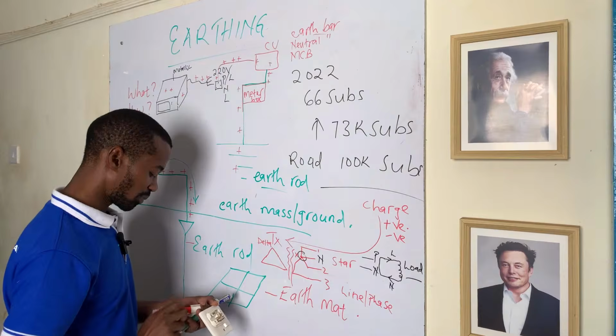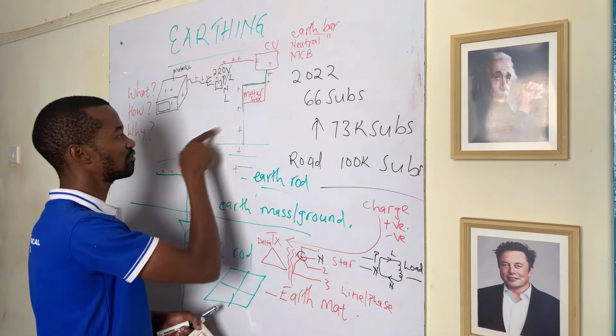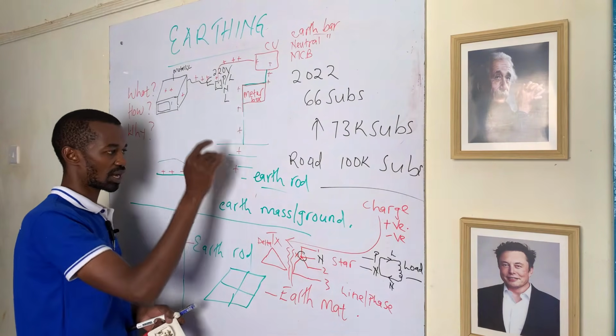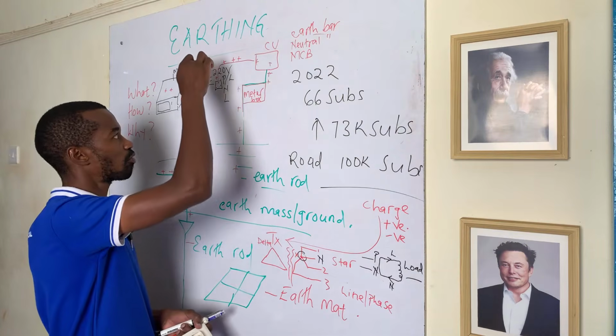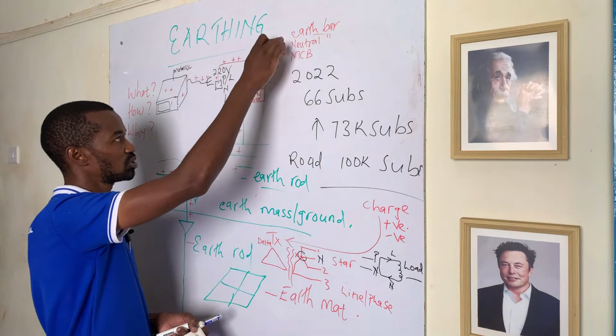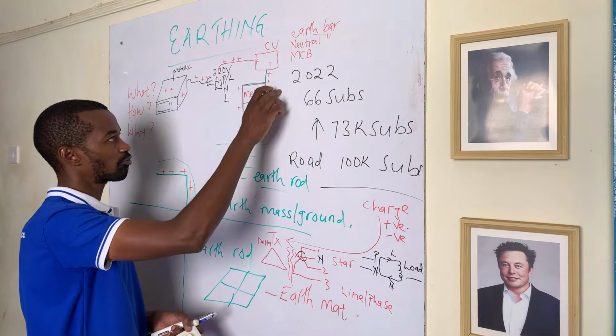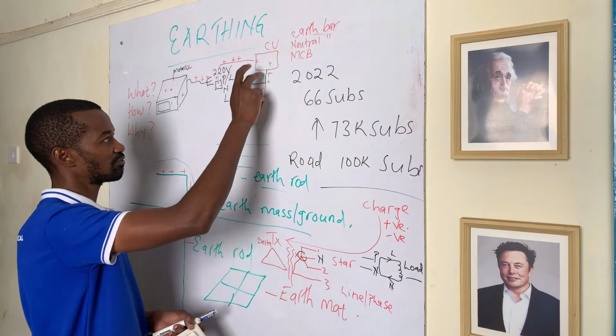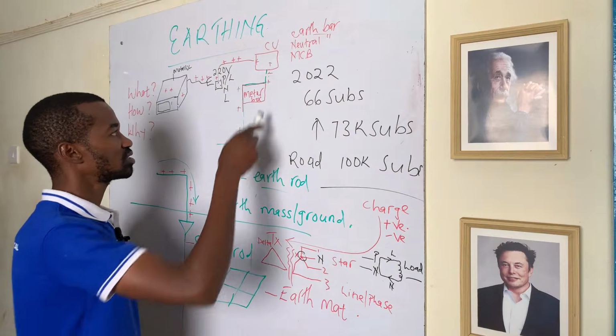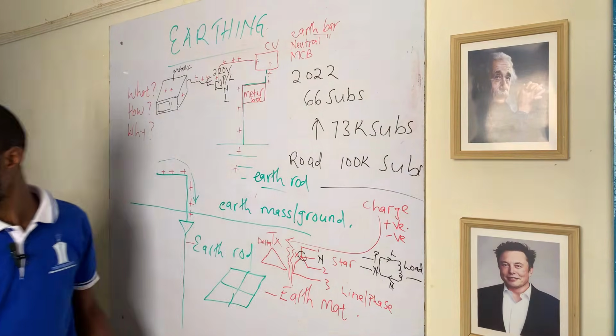Now, again, the customer is still not safe if this connection from the meter box to the earth is broken, or from the socket to the consumer unit is broken, or from the consumer unit to the meter box. If there is a break, or there is no continuity of the earth wire, it means that the customer will have it rough. And having it rough definitely means that the customer will be electrocuted.